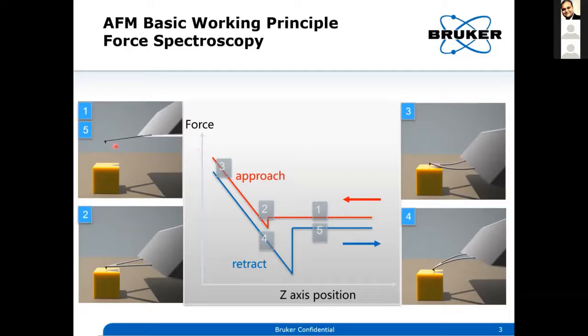The key differences are that here you have the cantilever, and then the end of the probe is there. These are typically silicon nitride, though of course you can have different materials. The tip is very small, right? We are talking a few nanometers. Let's say you're very far away from the sample, so the force on your tip is 0. There's no force on the sample.